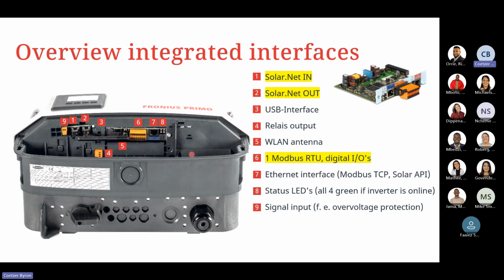So again, very similar to how the pilot device relies on an LED status of green and blue to notify us that the unit is 100% operational and communicating correctly, the same applies to the data manager card. If all 4 green LEDs are present, that means the unit is online, it has a complete Solar Net ring, and it also has a valid internet connection for the unit itself.